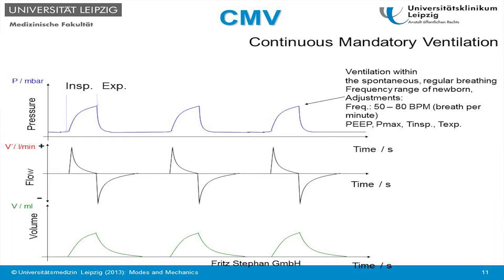Here you see several breaths. Here's the pressure, the flow, and the volume. It looks like what I've shown before. We call this continuous mandatory ventilation, or CMV, where every breath of a patient is done by the machine. The patient usually has not much influence on what's going on, and the patient is best off just by tolerating this and not trying to breathe in between.